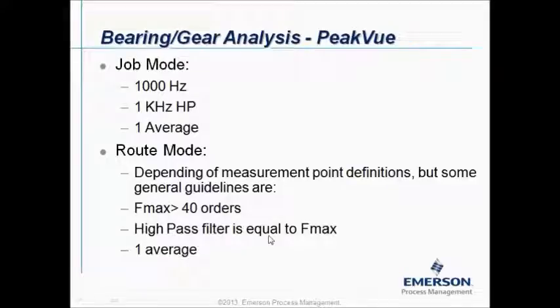A high pass filter is normally more or less equal to the Fmax. So if your Fmax is 1000 Hz the high pass filter will be 1000 Hz. If the Fmax is 2000 Hz the high pass filter will be 2000 Hz. And in PeakVue measurements, very importantly, we will always collect only one average.